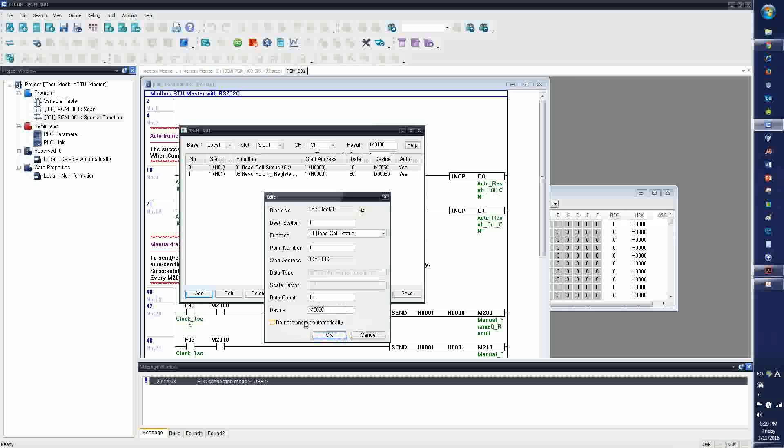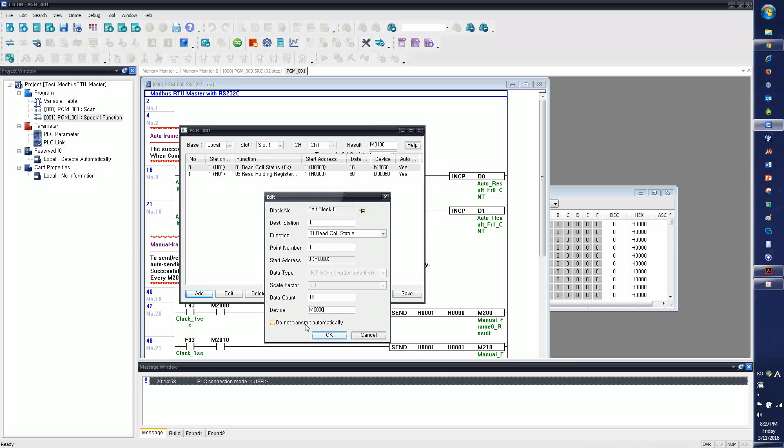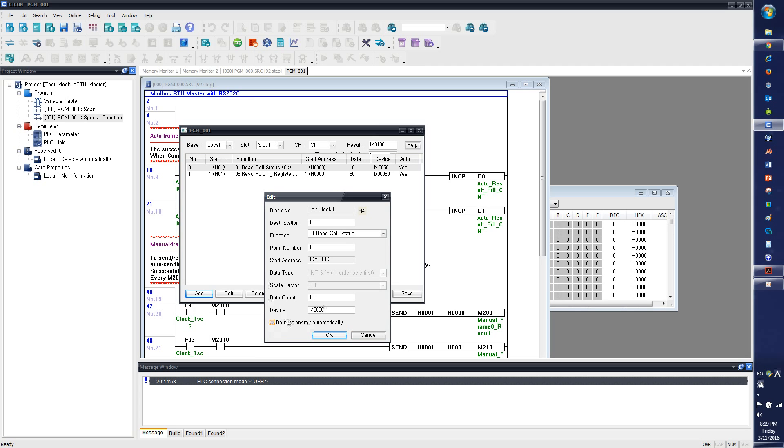The default setting for the Modbus RTU master is to send and receive communication frames automatically. But if you intend to use it on manual mode, instead of automatic mode, then when you click this, it will be operated by manual. You have to use the send instruction to send and receive the communication frame. But in this tutorial, we will use only the automatic sending and receiving mode.